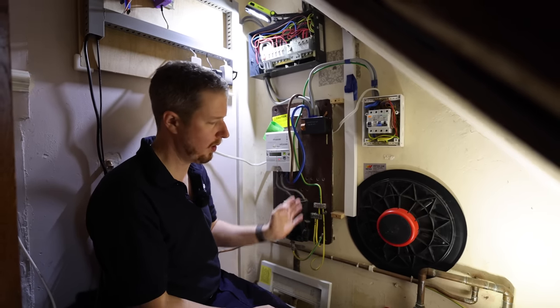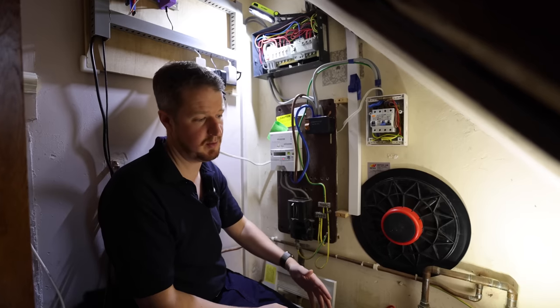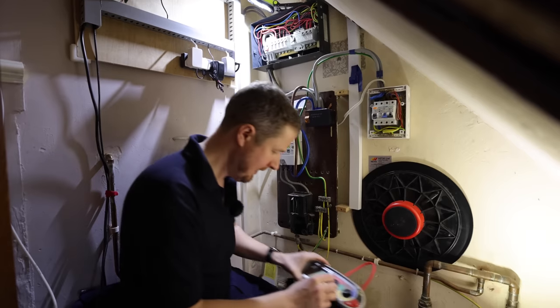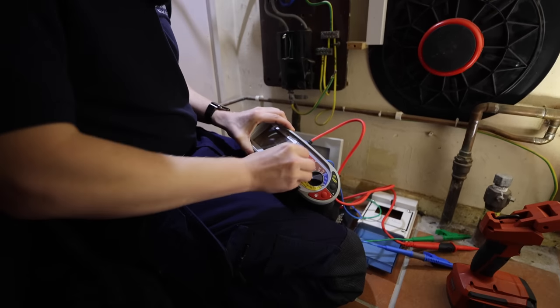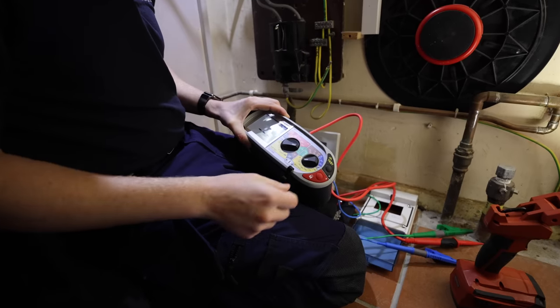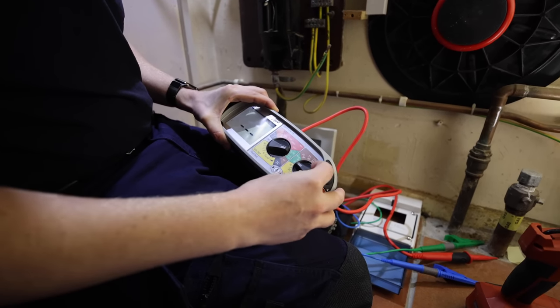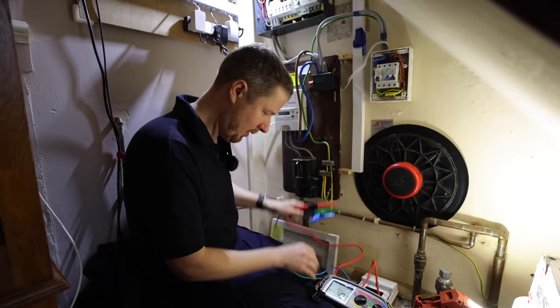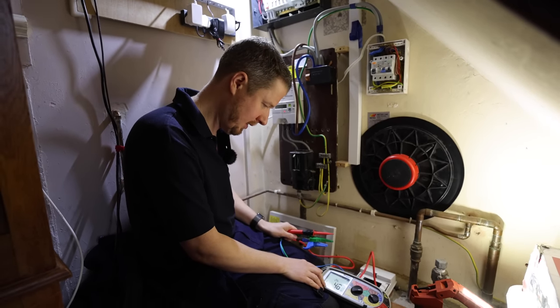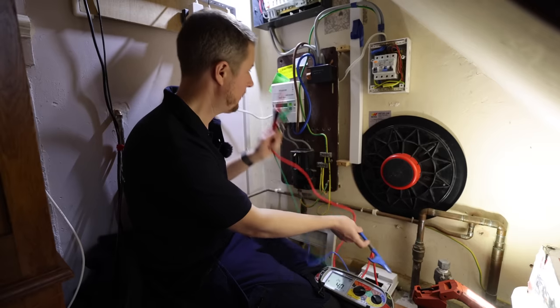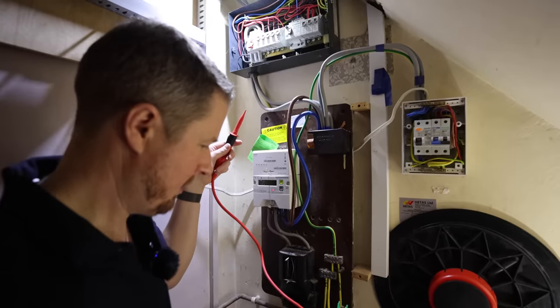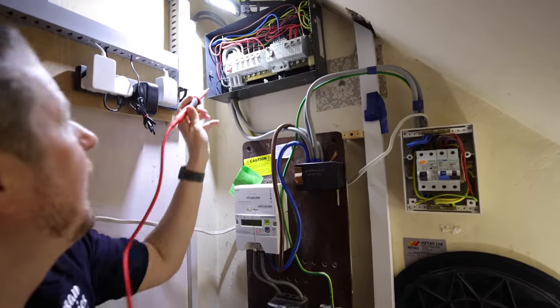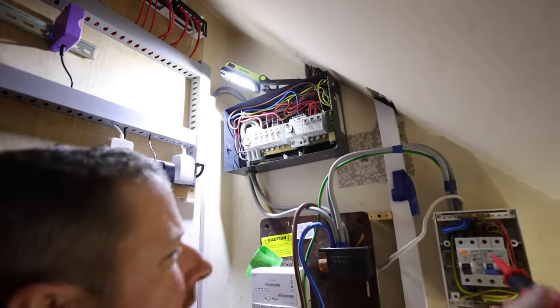The reason for that is that we don't want any parallel paths. We're only measuring the main earth coming in, we're not getting any parallel paths through any bonding connections which might be going into the ground through the pipes. So we're going to turn our tester on to the Zs setting, and we've got a three-lead option, but we can actually do the two-lead high current test for this.